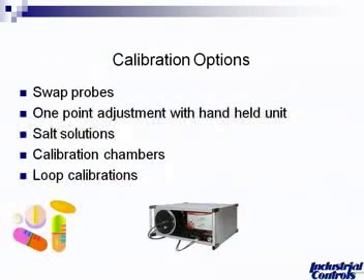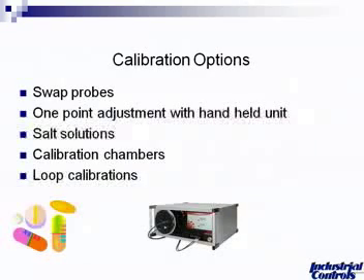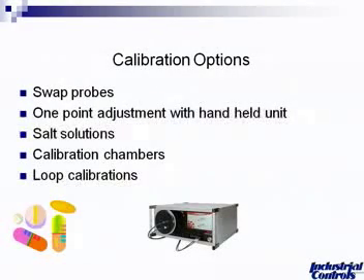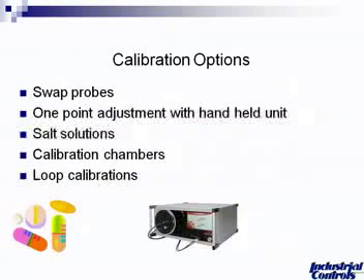There are salt solutions available for calibration. Different manufacturers provide different versions — there are saturated salts, which you may have to prepare yourself, and different salts generate different humidities in an enclosed environment. There are also unsaturated salts; some are prepared for you so you don't introduce contamination that could throw off the value. They're good, they're inexpensive, and they can be accurate if used properly, but they take time.